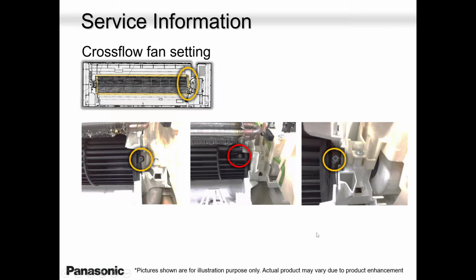We had a call 2 weeks ago, I think. There was a unit shipped. Now we are blaming the shipment. We don't know if it's the shipment or the manufacturer, but we are hoping that it's the shipment. And guess what? The blower wheel on the left hand side came out of the bushing. So when the unit was turned on, it was noisy. So the guy sent me a video, and I explained to him, please check the bushing on the left hand side. The shaft may have come off. And right enough, the bushing was out. So he put it back and everything was good. Everything was perfect.